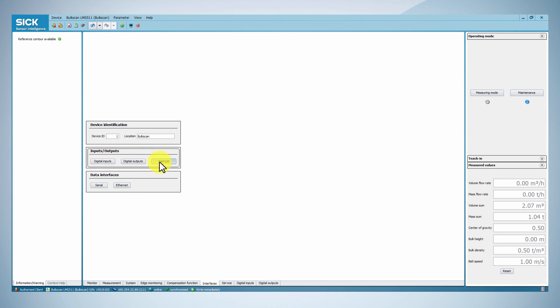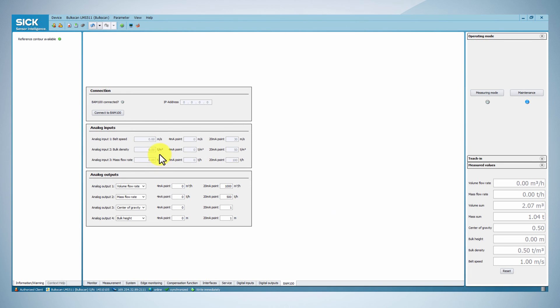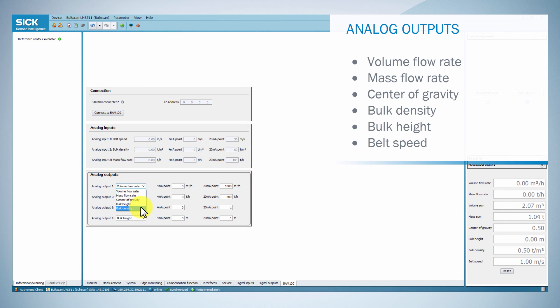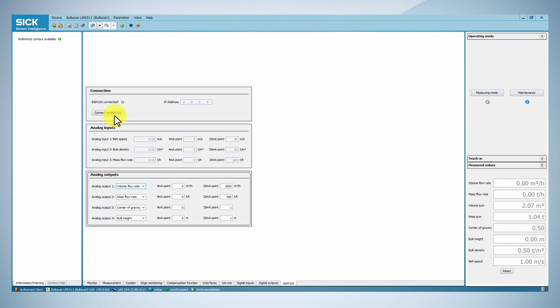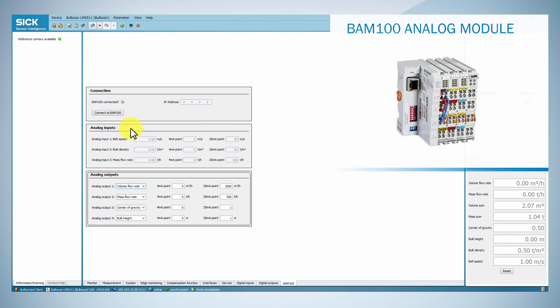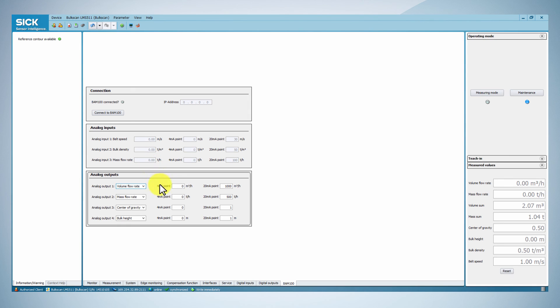The Bulkscan can read inputs and outputs analog 4 to 20 milliamps per value via the analog module BAM100. To configure the module BAM100, go to the Interface tab and in the Inputs-Outputs box click the BAM100 button. Then, you can configure the analog inputs and outputs.